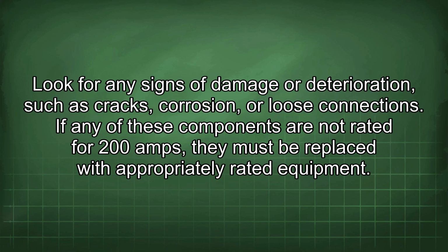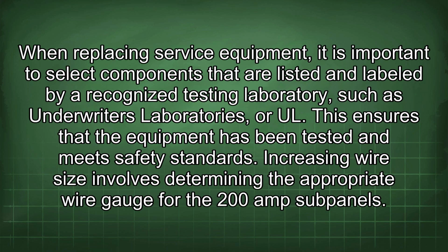If any of these components are not rated for 200 amps, they must be replaced with appropriately rated equipment. When replacing service equipment, it is important to select components that are listed and labeled by a recognized testing laboratory such as Underwriters Laboratories, or UL. This ensures that the equipment has been tested and meets safety standards.